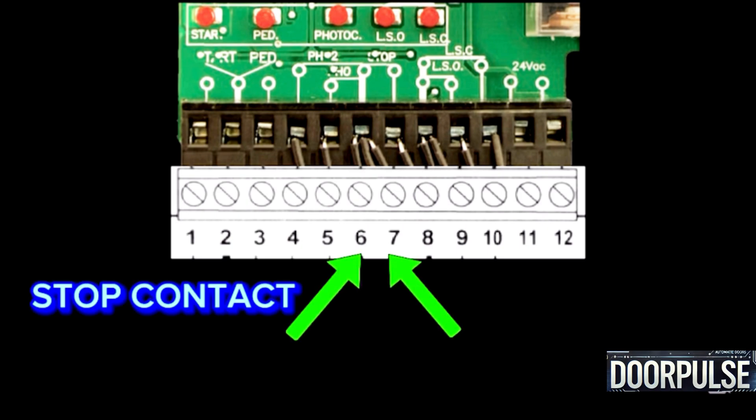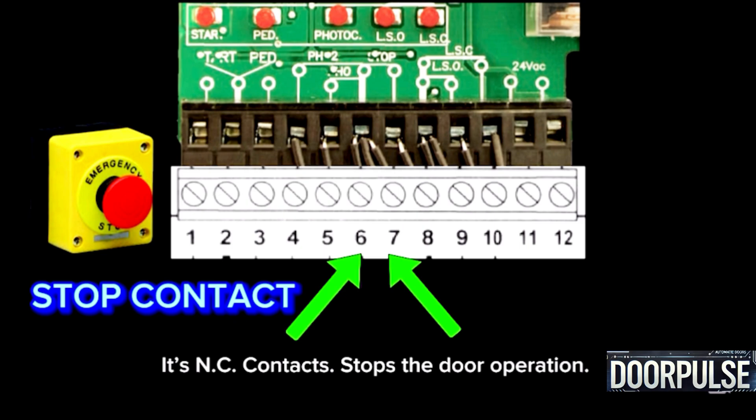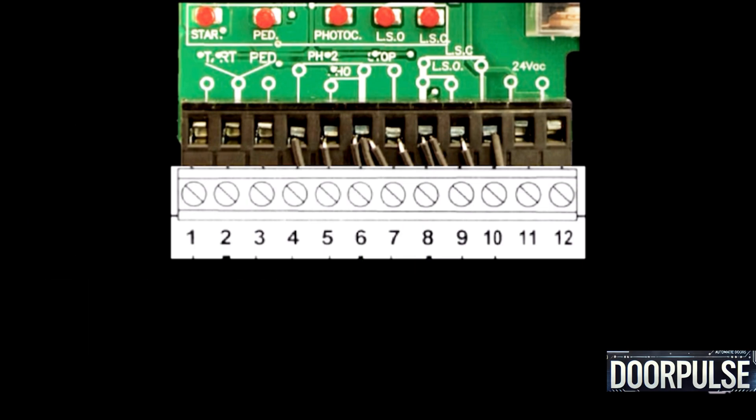Terminals 7 and 6: Stop contact. It uses NC contacts and stops the door operation. Use a bridge when not in use. Terminal 6 is common and Terminal 7 is the NC contacts input; Terminal 6 is common for Terminal 7.